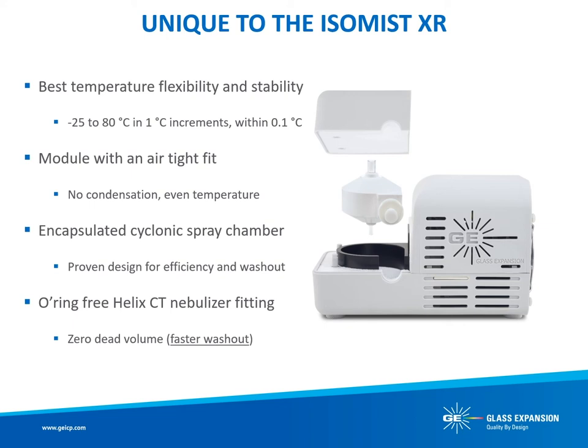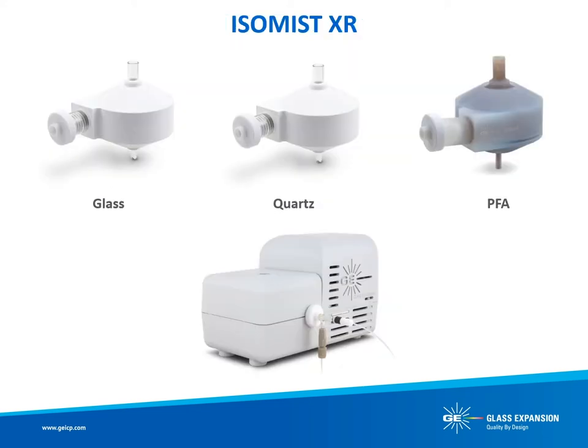The benefits of the Isomist XR include the ability to analyze volatile organics, enhance sensitivity for limited-volume samples, reduce isobaric oxide interferences, and increase the chance of passing QC checks by maintaining a constant temperature. It also provides a record of the temperature for regulatory compliance and eliminates temperature drift. Each Isomist XR is customized for the particular make and model of ICP-OES or ICP-MS instrument for which it will be used.